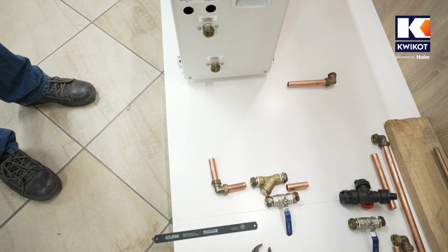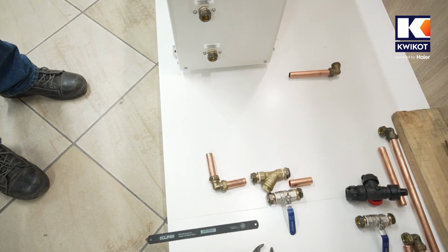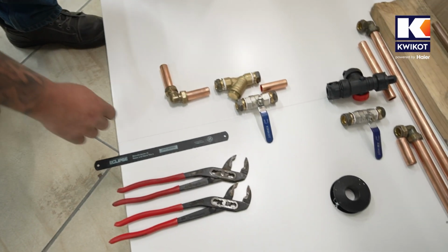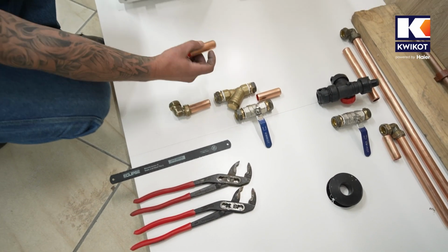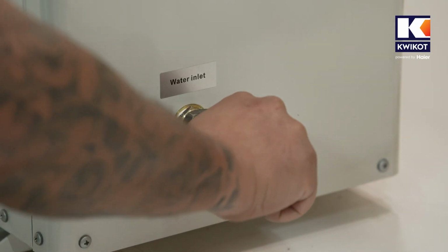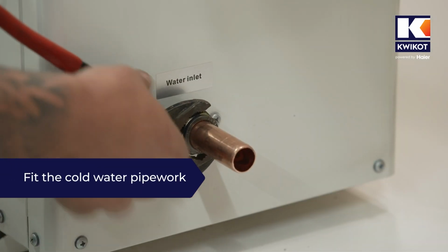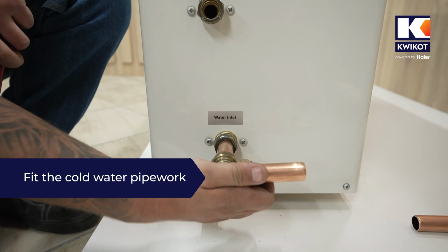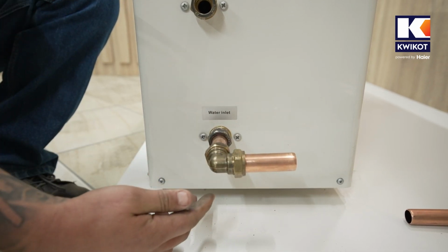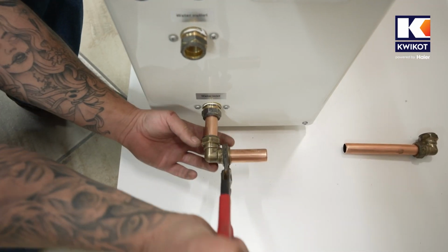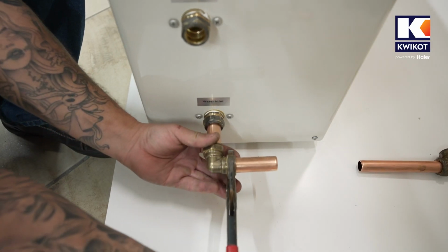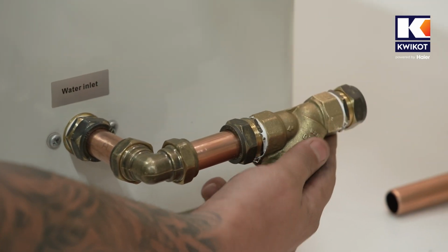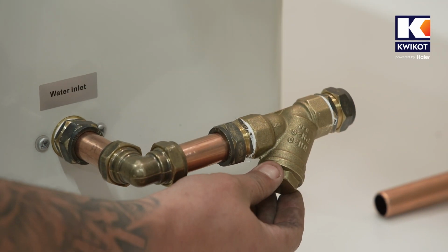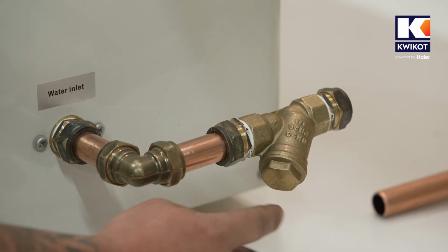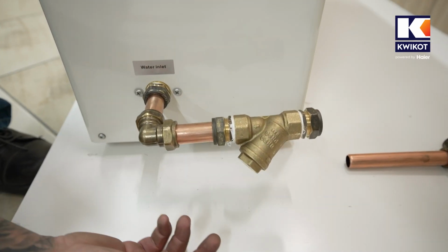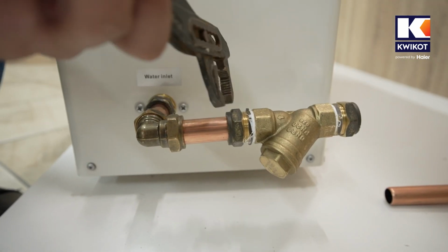As you can see, we have pre-cut the pipes to the required lengths in order to speed up the pipework process. We begin by fitting this length into the inlet socket and tighten the fitting. And then next we fit a Conex elbow and tighten the first fitting, and then we tighten the other fitting. And next we fit the inline strainer. The strainer must be pointed down so that when you clean the inside of the strainer cylinder, the dirt will drain downwards.